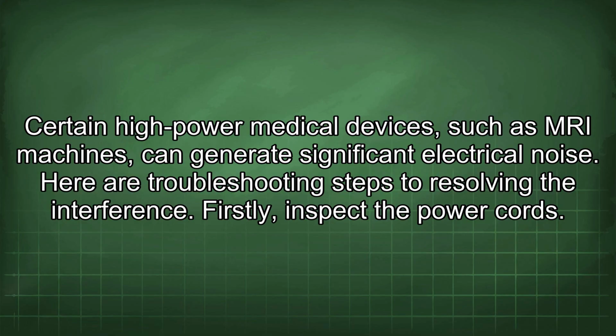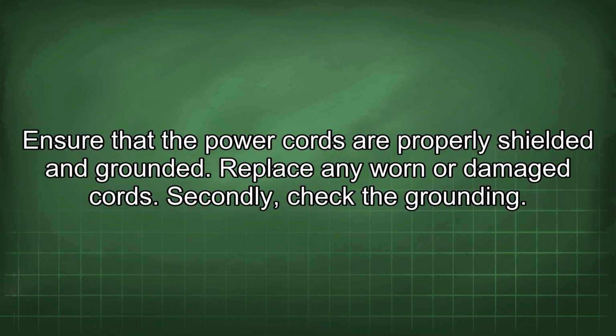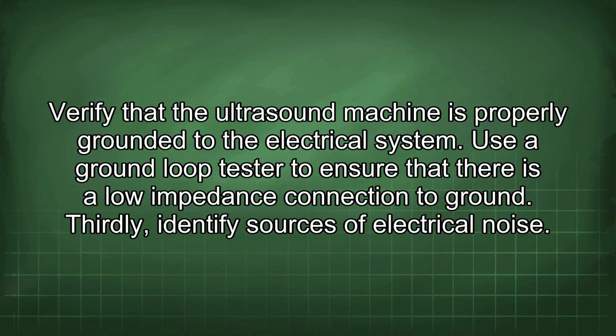Firstly, inspect the power cords. Ensure that the power cords are properly shielded and grounded. Replace any worn or damaged cords. Secondly, check the grounding. Verify that the ultrasound machine is properly grounded to the electrical system. Use a ground loop tester to ensure that there is a low impedance connection to ground.